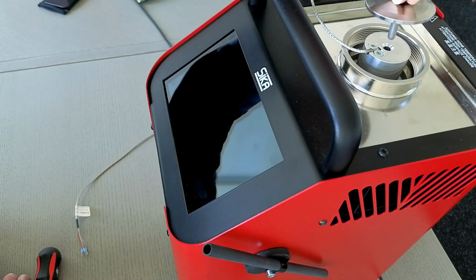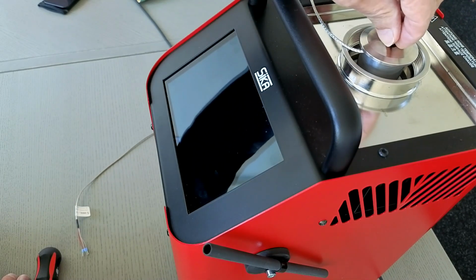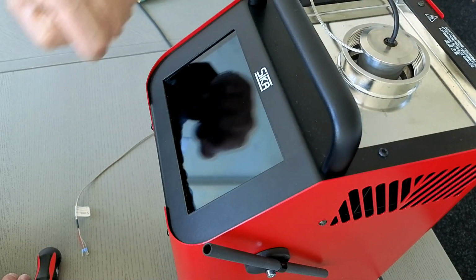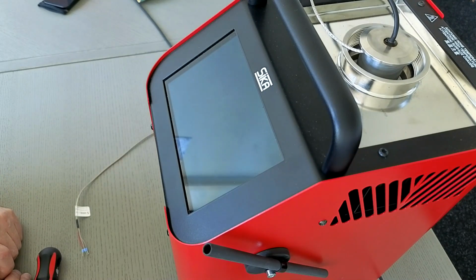This means the sensor fits flat, and the device under test and the reference sensor are on the same level. With this setup, you can carry out the calibration.